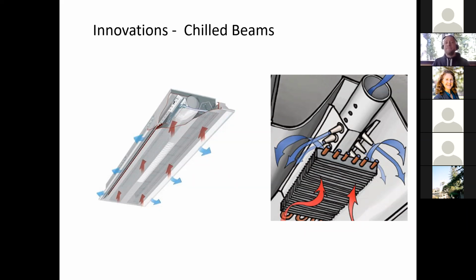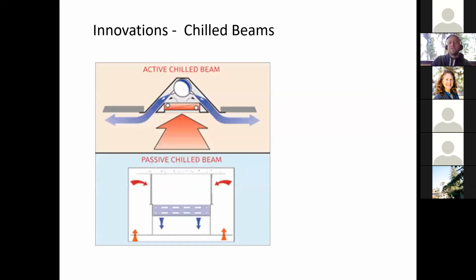They're very quiet, but they work especially well. They come in two varieties. You have active chilled beams and passive chilled beams. So active chilled beams are the ones I've generally been talking about, where you take your ventilation air and blow through them. But there's another class of chilled beams that have quite a bit less capacity, called passive chilled beams.